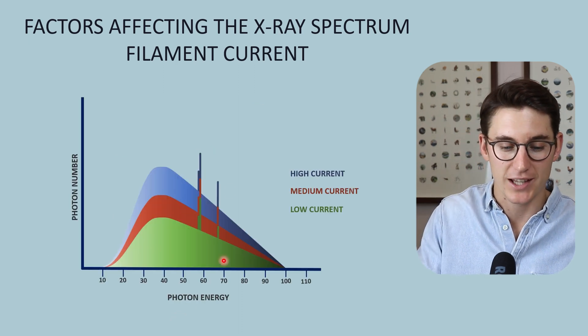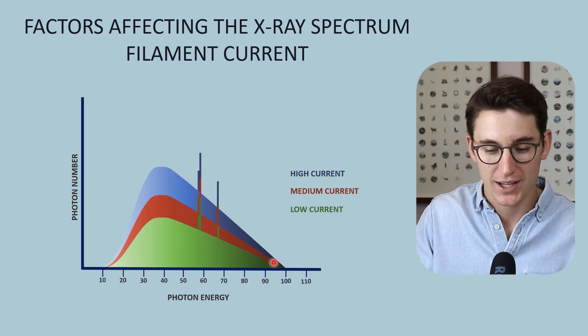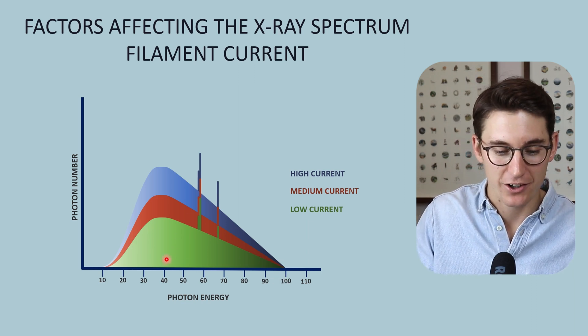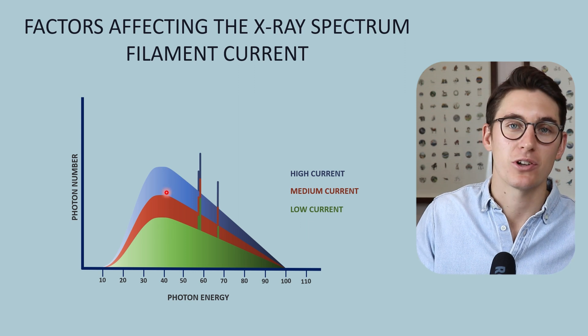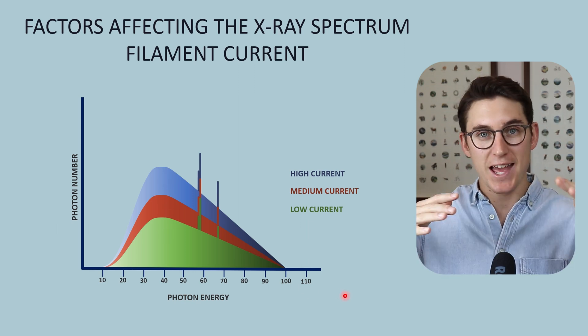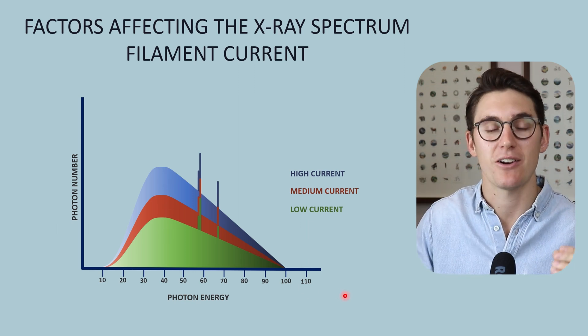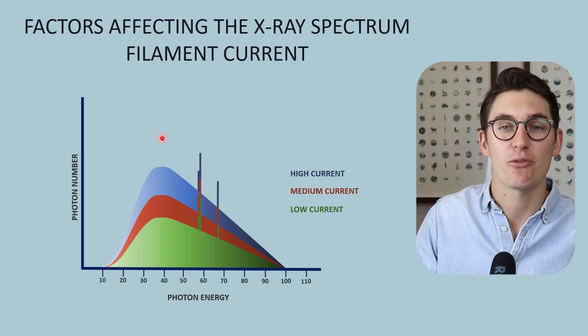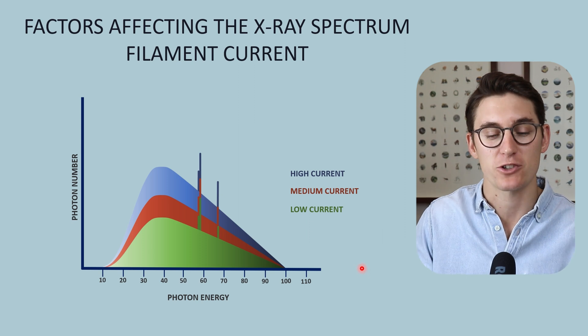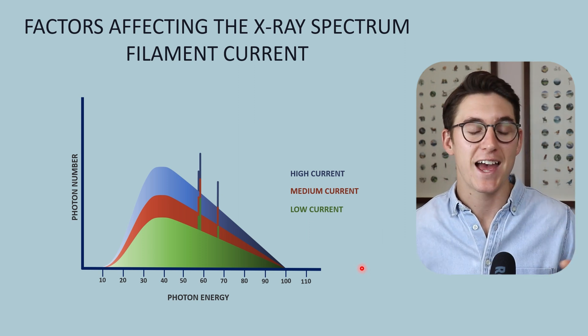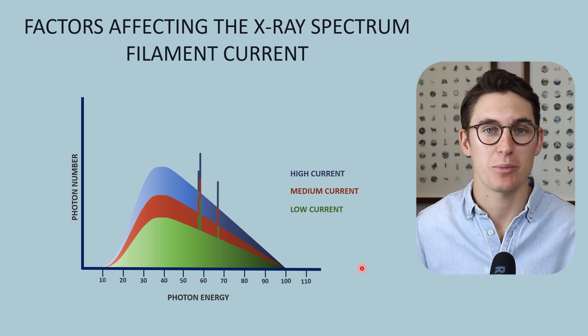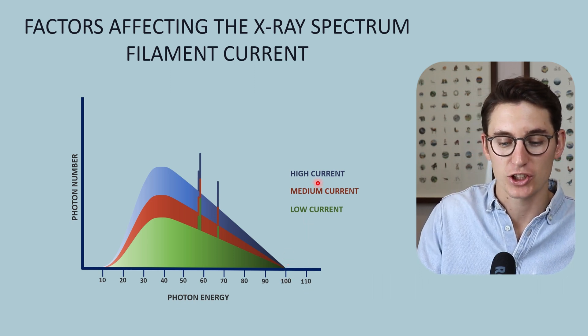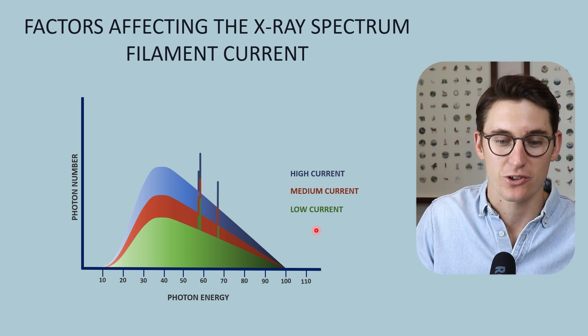Let's look at that on our x-ray spectrum graph. Here in green is a low current x-ray spectrum. As we increase that current, we increase our photon number — we are increasing the area under the curve, increasing our x-ray beam quantity. We are not changing the average energy of this x-ray beam spectrum, so a change in filament current has no effect on x-ray beam quality. This maximum photon energy does not change as our filament current increases.